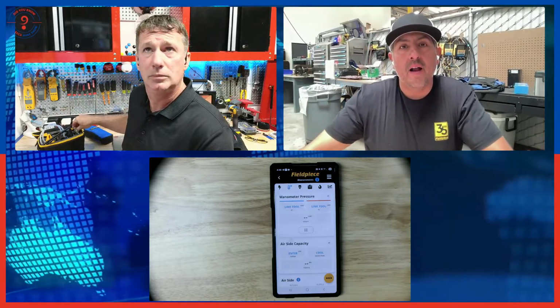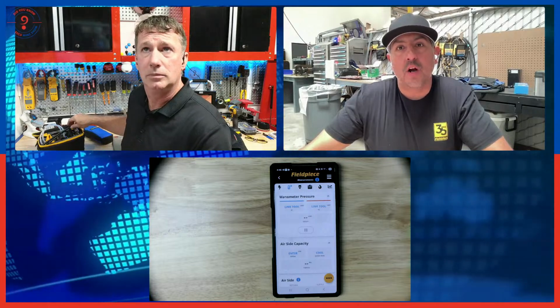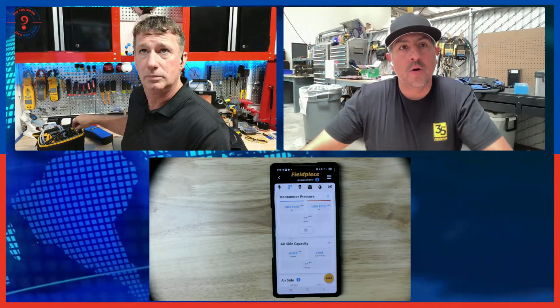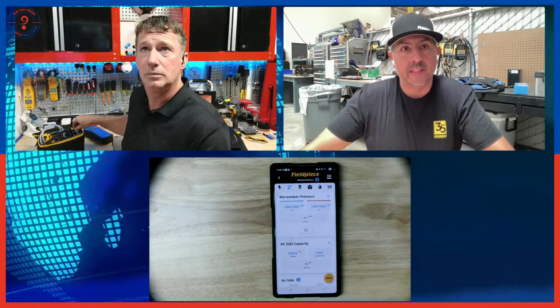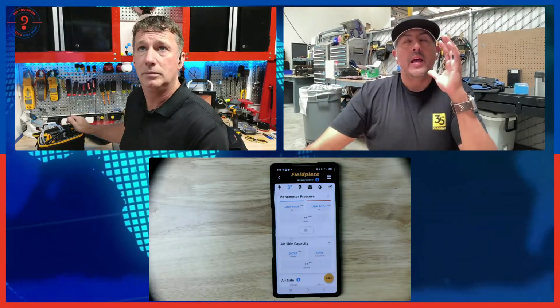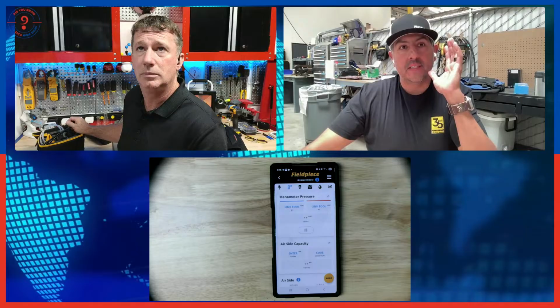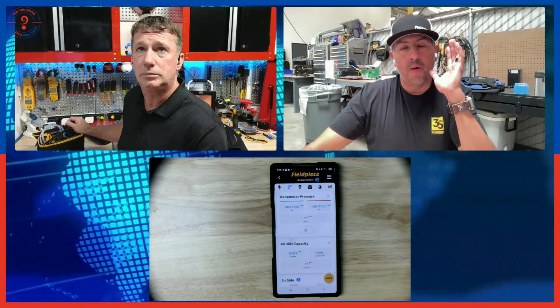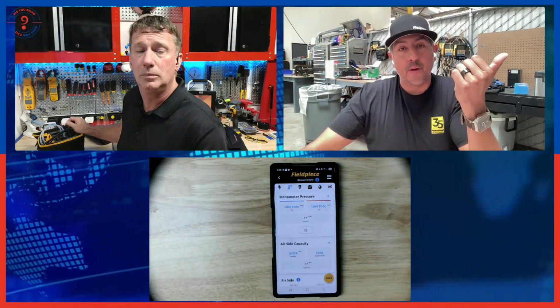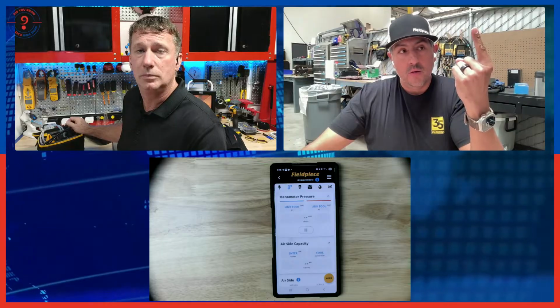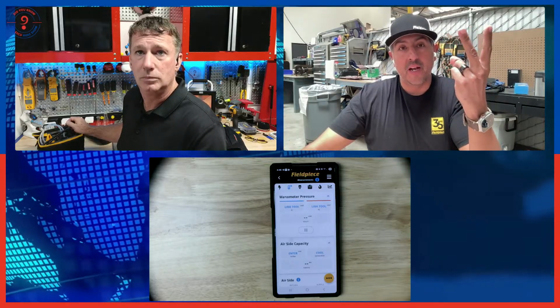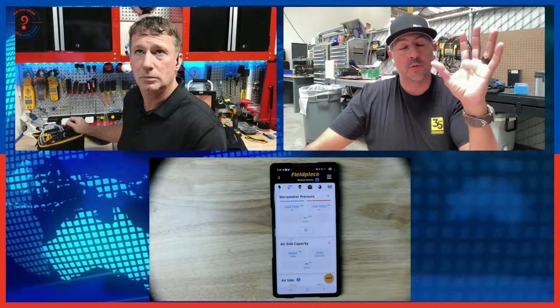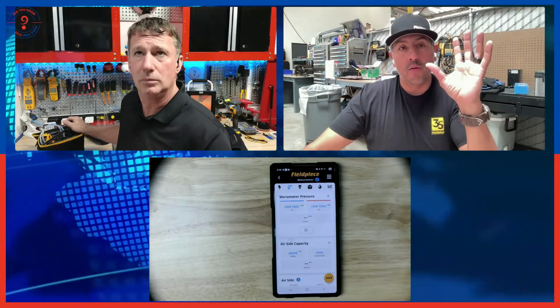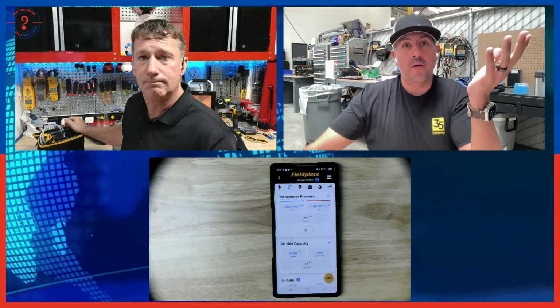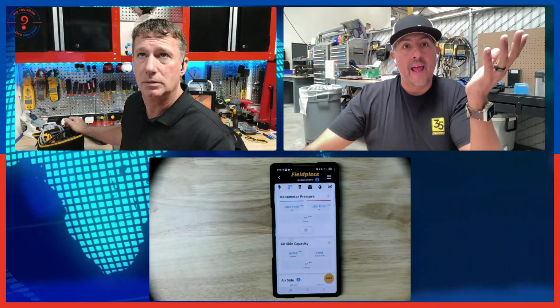To me, I always start with the big why, right? So why are we even doing this? Well, in order to properly commission a system and confirm that we have proper operation, we got to look at three things. We got to look at the airflow, we got to look at the refrigerant charge, and we got to make sure all the electrical components are wired correctly and that we have power in the right spots where we need the power, right? Sure.